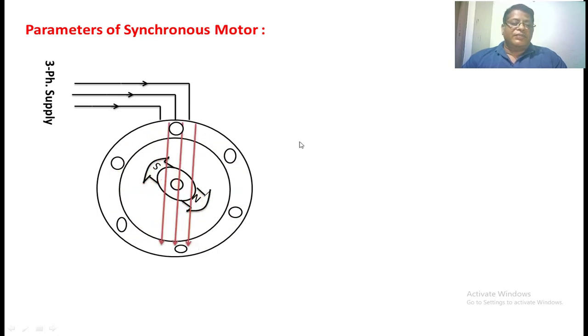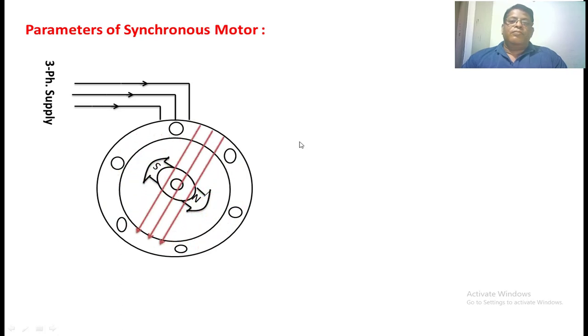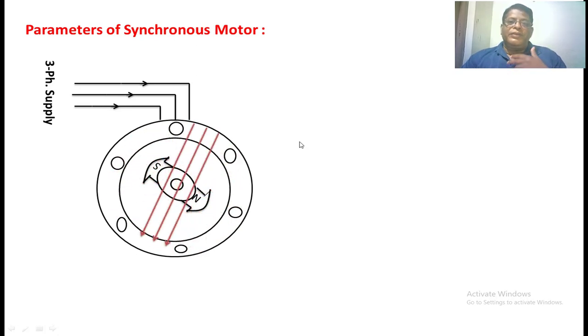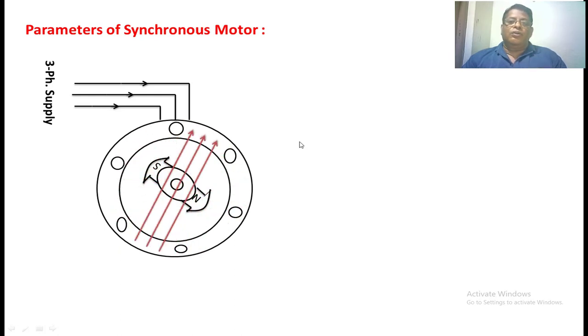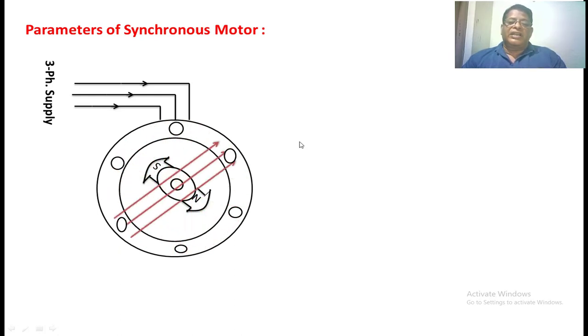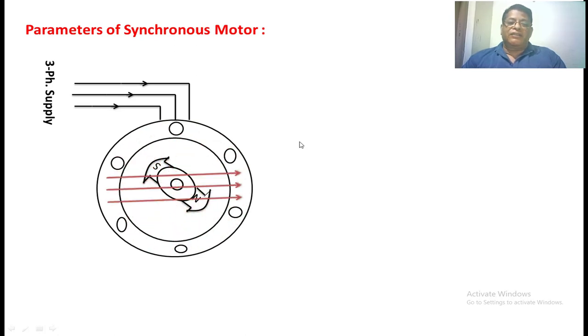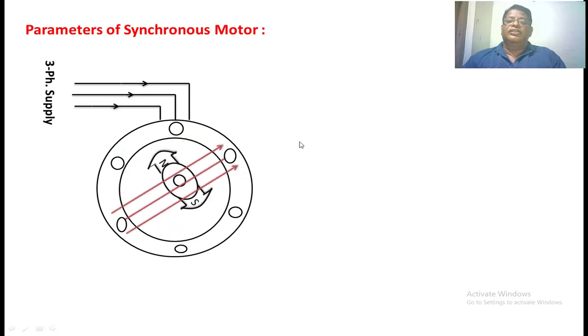A rotating field is created from the stator winding which is running at synchronous speed. By means of external means, we are rotating the rotor near to the synchronous speed. Once the rotor speed is near to synchronous speed, at that point we give the DC excitation to the rotor. There is a magnetic locking between the stator flux and the rotor, so the rotor will also be running in the same direction as the stator flux, and the speed is also the synchronous speed.